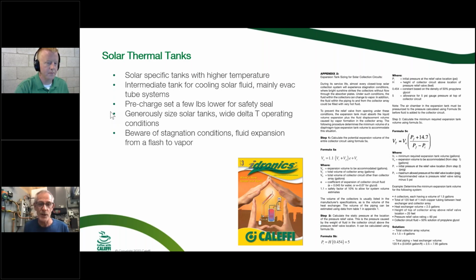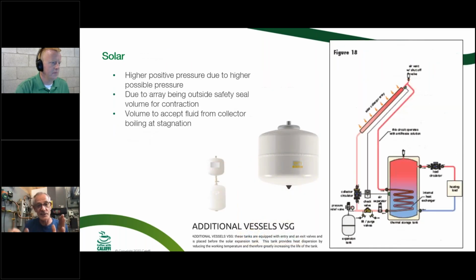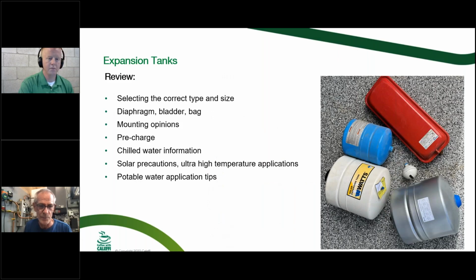Also on those evacuated tube systems especially, they do make a tank that you could put between your expansion tank and your piping that's actually, oh, there it is, I put it in there. That little tank is a cool down vessel. It's intended to take that high temperature, that shot of glycol that's coming out of that collector at maybe 300 degrees, and cool it off a little bit before it gets into the diaphragm. The solar ones typically have a higher temperature diaphragm, certainly not 300-degree temperature, but that's one way. I've seen people, even in the MTRL book on some of these bigger systems, show a piece of fin tube on the line between the boiler, the solar, and the tank to just dissipate some of that heat, so we're not shocking that tank with that super high temperature. That happens to be a Zilmet brand, that intermediate vessel there.